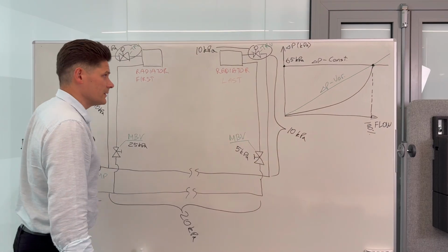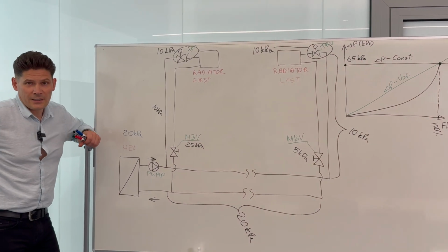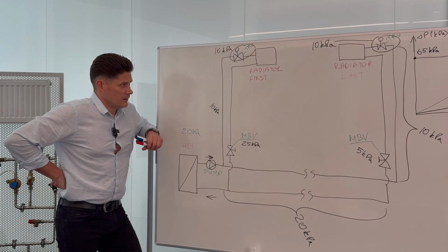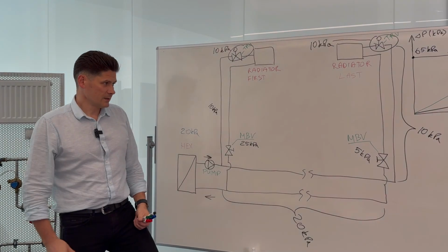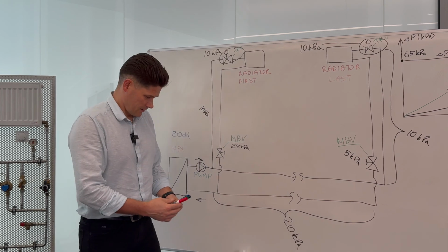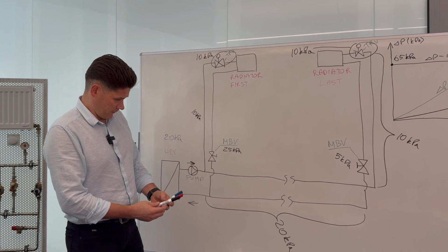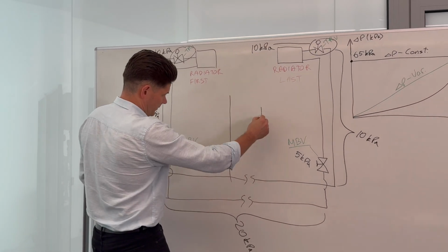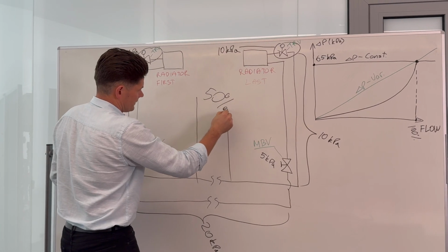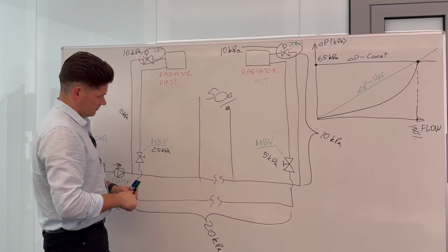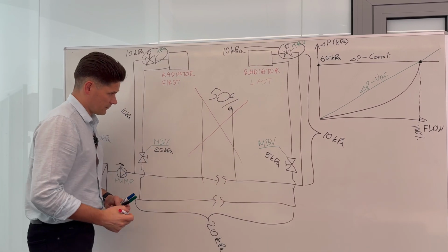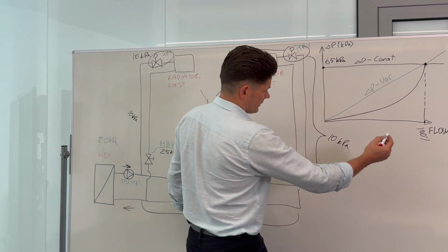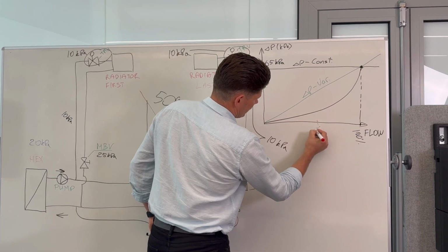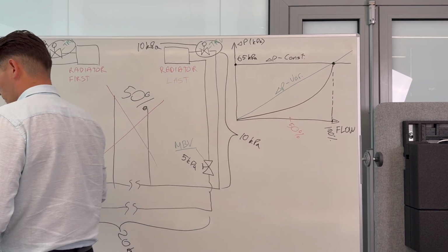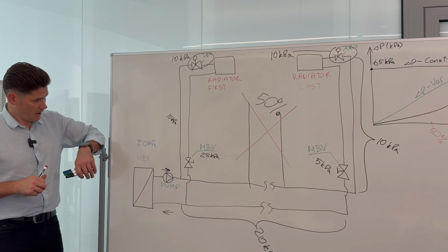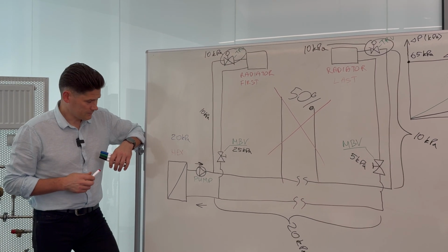But not always, and let's see how the system will work on a partial load. Let's say on one side of the building, the sun starts shining, and we don't need heating in this part of the building. So let's say here we have some 50% of risers, and those risers just close, thermostatic radiator valves close those risers, and now I have not 100% flow, but all I need is 50%. So let's say I need half. My system is at half partial load, and let's see how it is working at partial load.